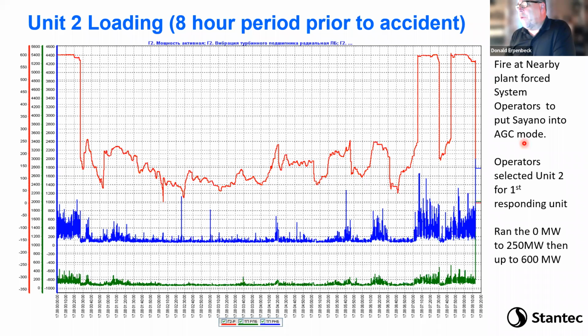So for some reason, when they shifted the AGC to Sayano, they picked unit 2 for the first responding unit in AGC. With the vibration going on, to be honest, it should have been the last responding unit. They should have never picked unit 2. They should have picked a different unit, but they figured, since the operators didn't know any better, that since the unit had just been refurbished, it was in the best shape. And they had turned off the vibration alarms because they were continually going off.